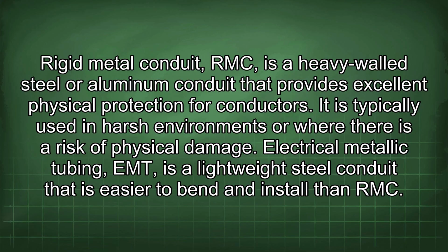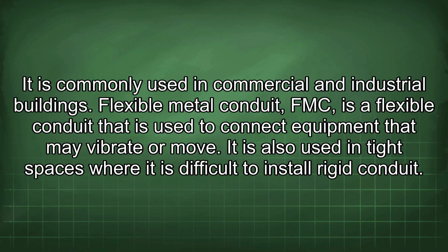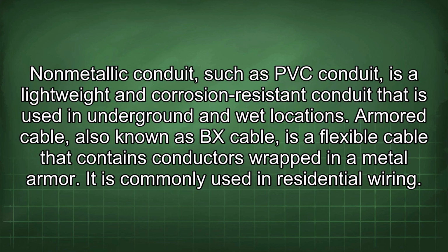Electrical metallic tubing, EMT, is a lightweight steel conduit that is easier to bend and install than RMC. It is commonly used in commercial and industrial buildings. Flexible metal conduit, FMC, is a flexible conduit that is used to connect equipment that may vibrate or move. It is also used in tight spaces where it is difficult to install rigid conduit. Non-metallic conduit, such as PVC conduit, is a lightweight and corrosion-resistant conduit that is used in underground and wet locations.